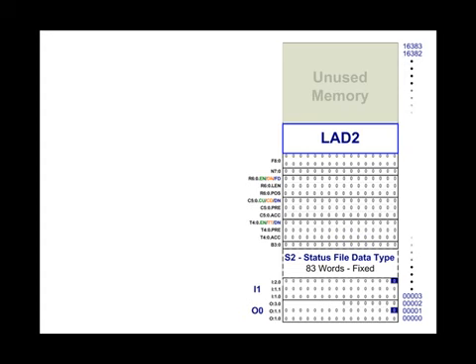For data files and program files, the file numbers are arbitrary. For data files, you can create new files numbered 9 through 255, and you can have any data file number without successive data files — for example, data file 47 without having files 9 through 46. For program files, you can create Ladder 3 through Ladder 255, such as Ladder 15 without program files 3 through 14. They are markers only — like flags on a golf course — and can be executed in any order. Ladder 2 is the only routine that always executes.